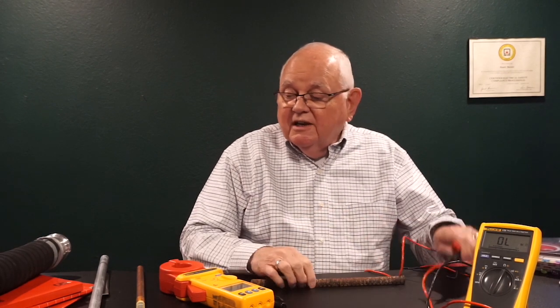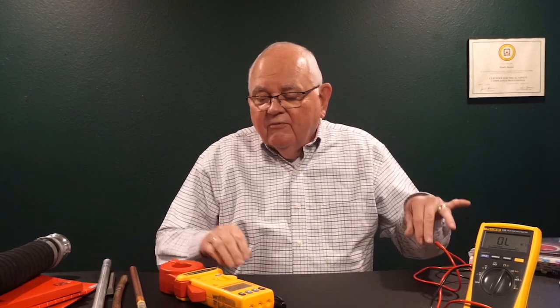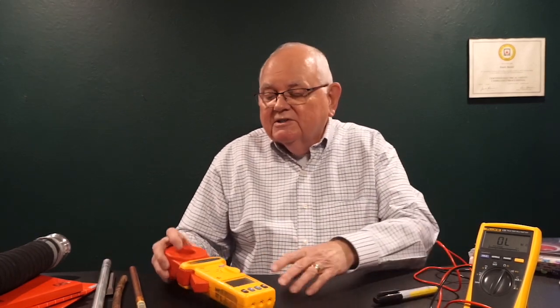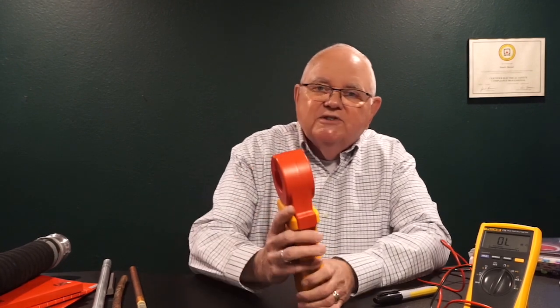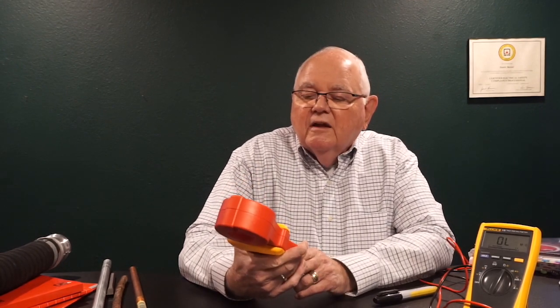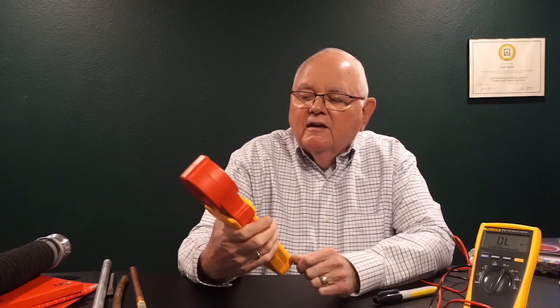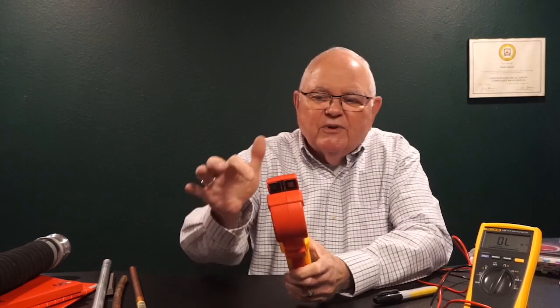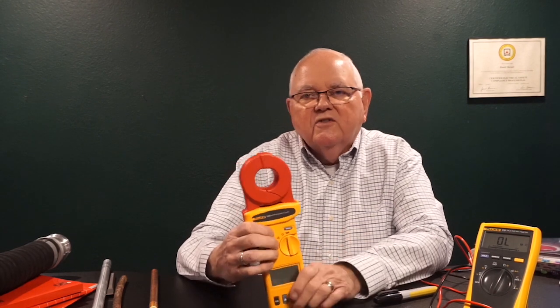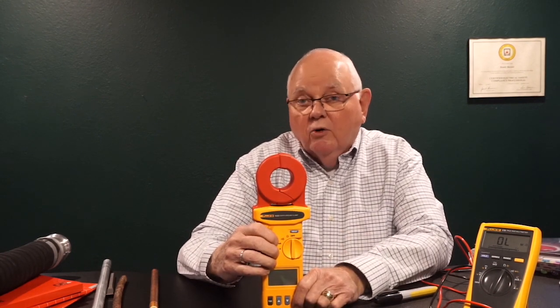So pretty interesting. Another item is that we have minimum requirements, or excuse me, maximum requirements, I guess we should say, in the NEC for resistance into the earth. And this particular meter reads that resistance into the earth. Okay. And so if you could open it up and look on the inside, it's pretty hard to see, but there are two separate coils in there. One coil produces a voltage, which induces current into my grounding electrode conductor, whatever it is that I'm measuring. And then the other coil reads the amount of current that flows. And of course, through the electronics, it then reads out in ohms of resistance.